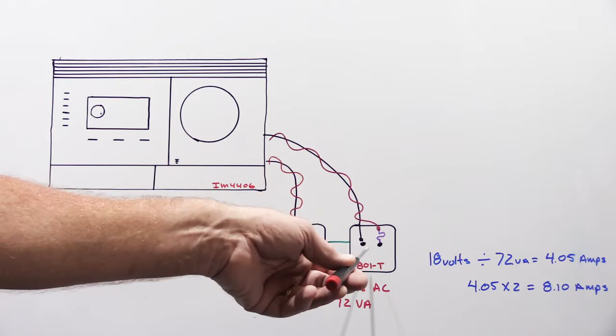This presents a dilemma, and the dilemma is, why did the transformer fail? Transformers don't typically fail all on their own. Transformers are usually a casualty of another problem. It's not common at all, based on historical and real world experience, for 801Ts to just suddenly go poof on their own and die. They have to be dead for a reason.